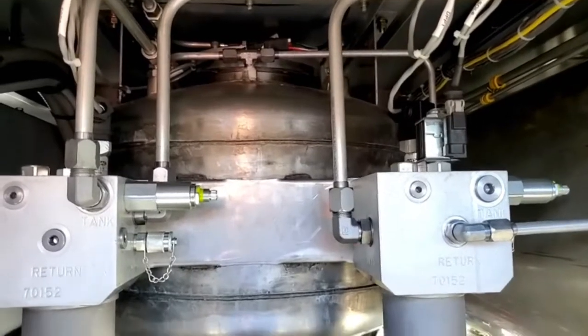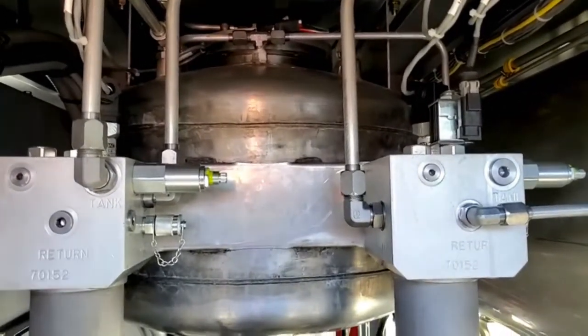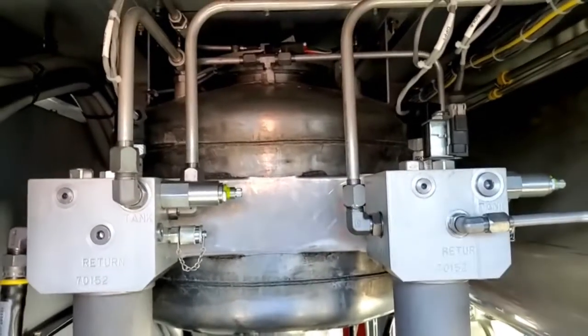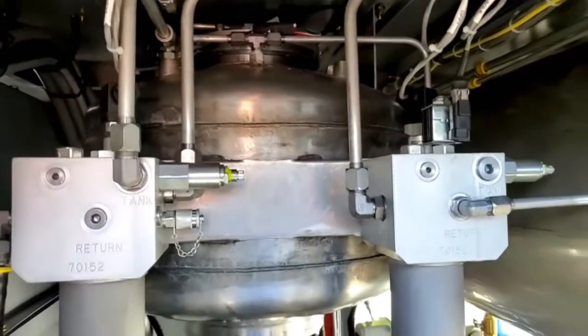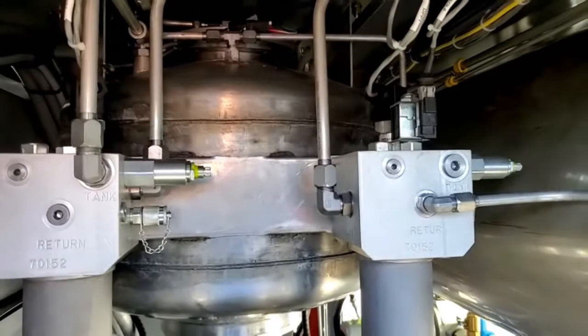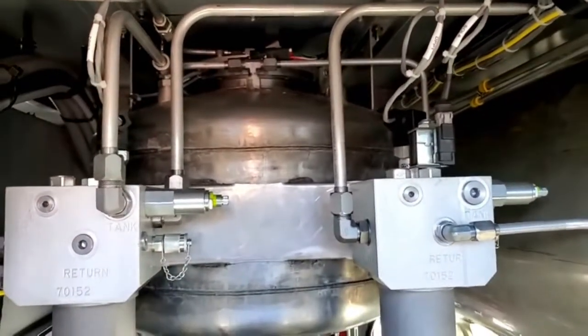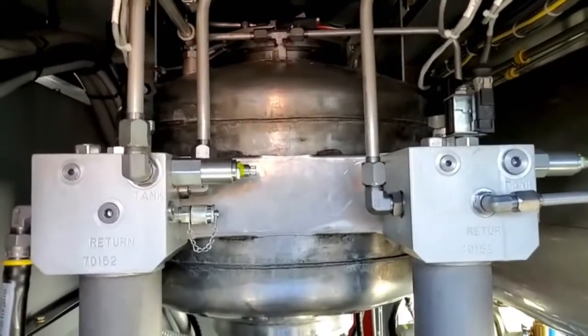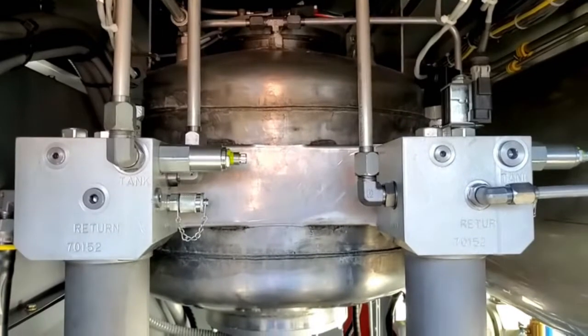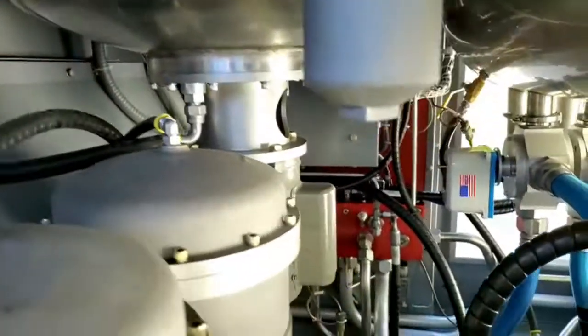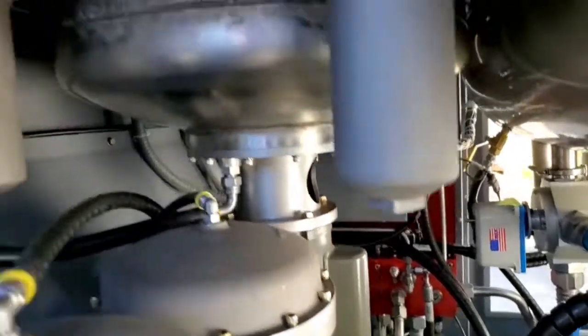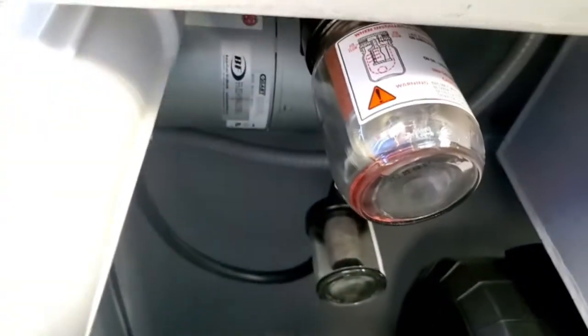Inside of the purification tank is a level switch. It has 4 floats on it, and each float does something a little bit different. When level number 1 is not illuminated, your charge pump will turn on and start filling the tank. Once it reaches level 2, your discharge pump will turn on and your vacuum pump will follow the discharge pump.